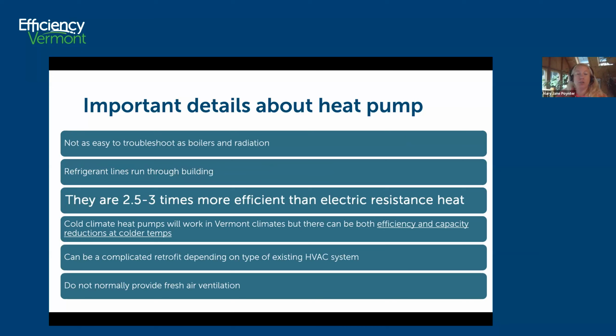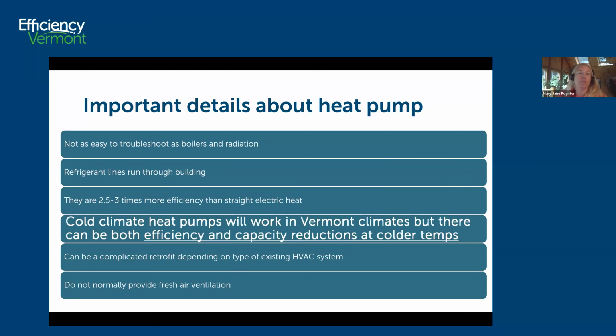Heat pumps are 2 to 3 times more efficient than electric resistance heat. That is a good thing to know. And oftentimes in new construction, heat pumps are paired with straight electric resistance heat. It's allowed by the energy code. But if you're doing a retrofit project, you can utilize the backup heating system, and that will allow you to not have to size down to the super coldest temperatures, because you have a backup heating system that you can utilize, which makes the whole thing a bit more cost effective.